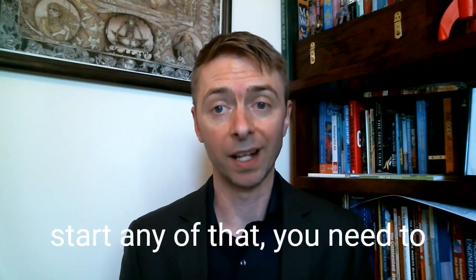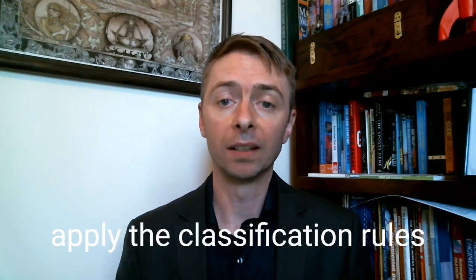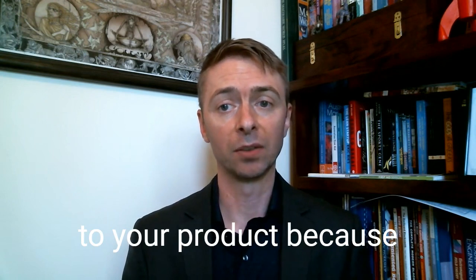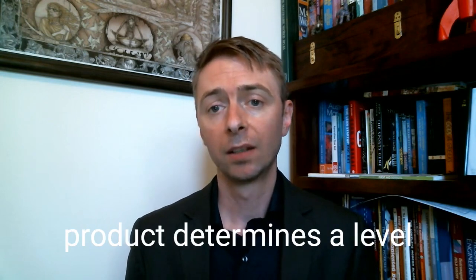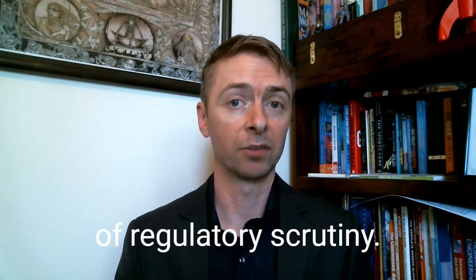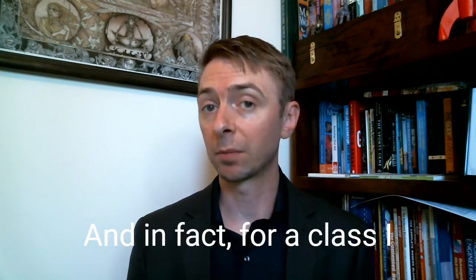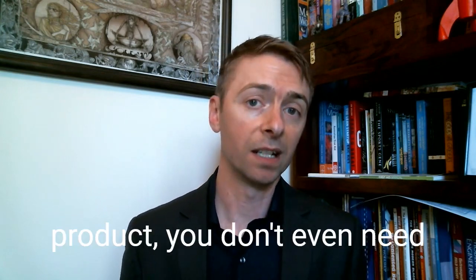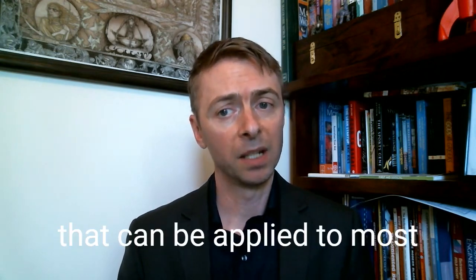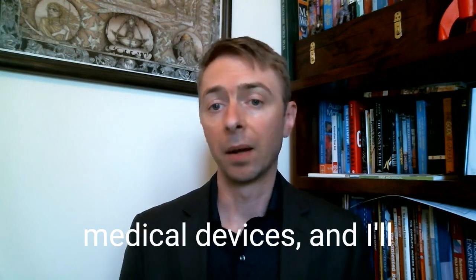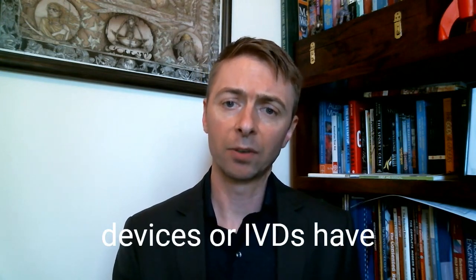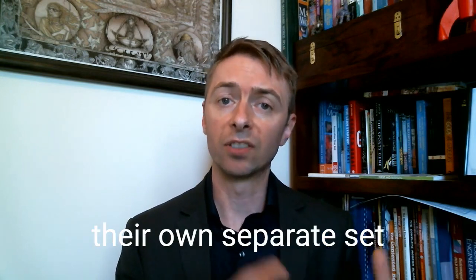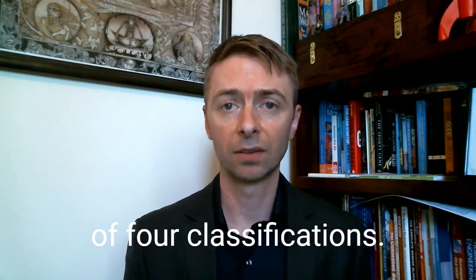However, before you can start any of that, you need to apply the classification rules to your product, because the classification of your product determines the level of regulatory scrutiny. And in fact, for a Class 1 product, you don't even need certification of your QMS. There are 5 classifications that can be applied to most medical devices, and I'll cover these in future videos. In vitro diagnostic medical devices, or IVDs, have their own separate set of 4 classifications.